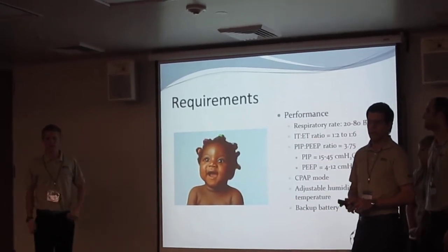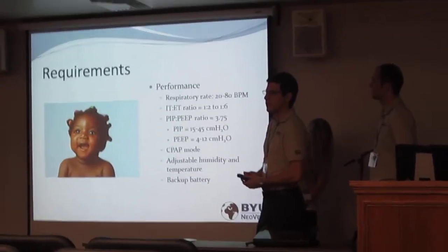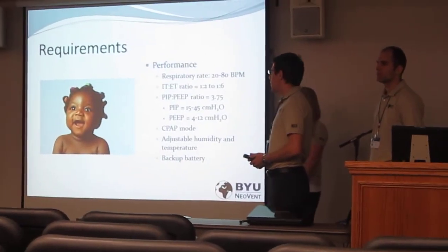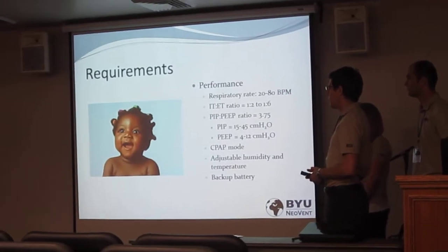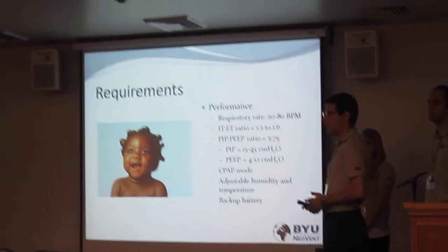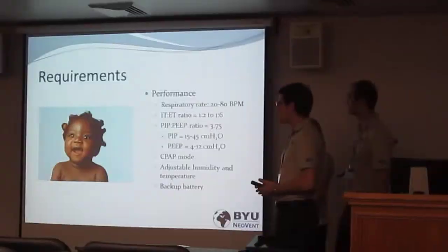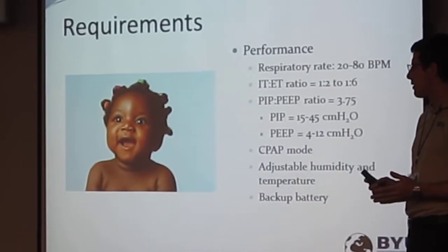So working with Dr. Goudet, a neonatologist, we've been able to come up with the following required performance characteristics for the ventilator that we're designing. We talked about the breathing rate. The respiratory rate is the number of breaths per minute. We want our ventilator to provide a waveform that has around 10 or 20 to 80 breaths per minute.